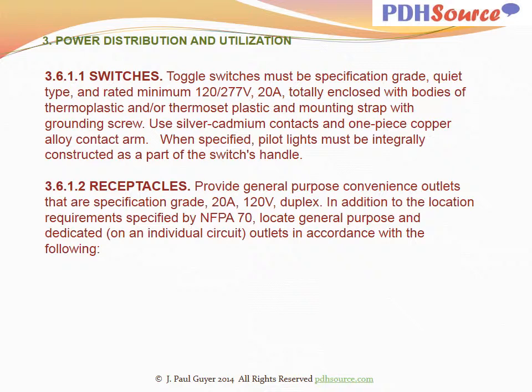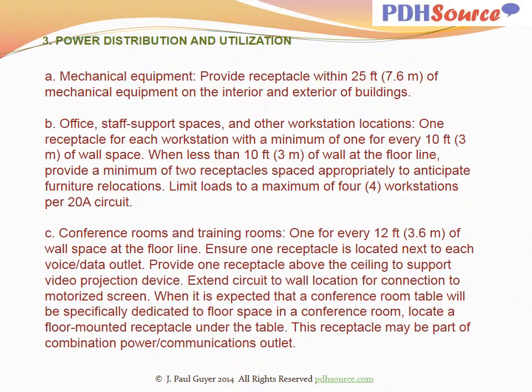Provide general purpose convenience outlets that are specification grade 20 amp 120 volt duplex. In addition to the location requirements specified by NFPA 70, locate general purpose and dedicated on an individual circuit outlets in accordance with the following. Mechanical equipment. Provide receptacles within 25 feet of mechanical equipment on the interior and exterior of buildings.